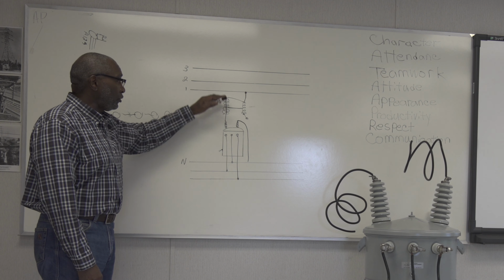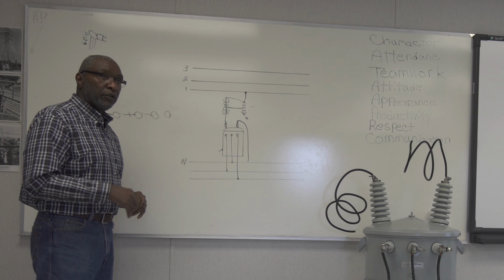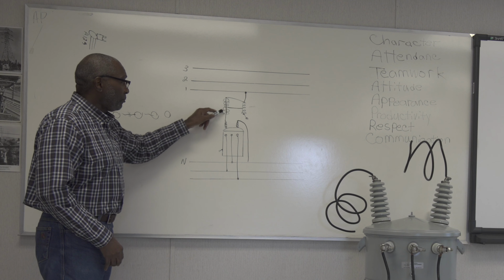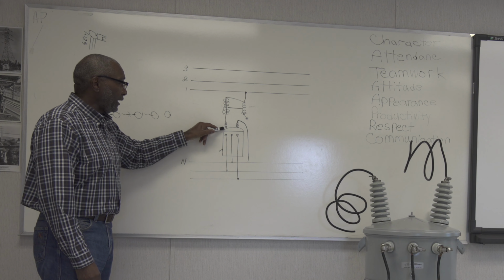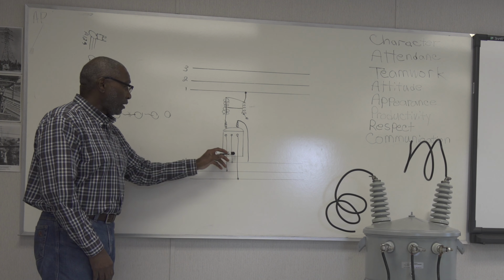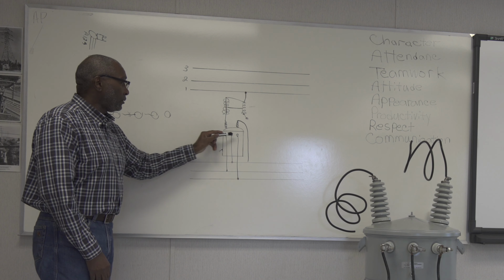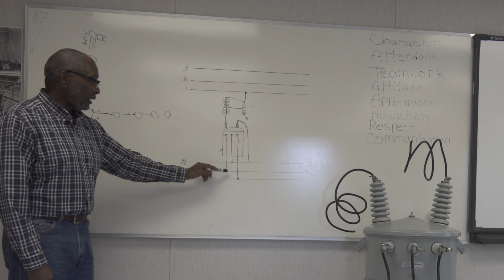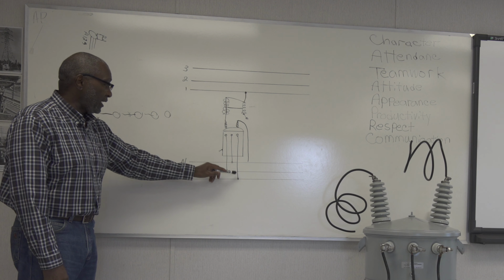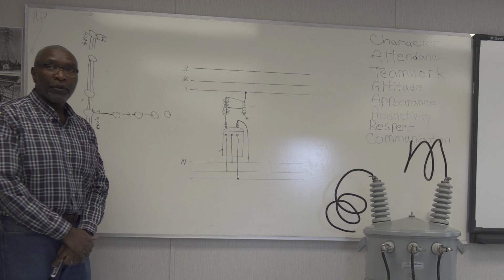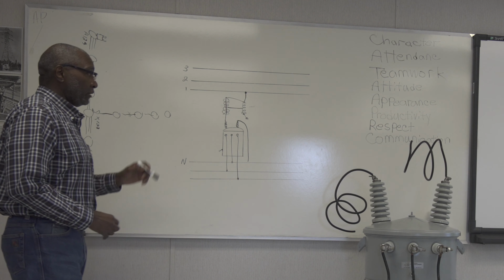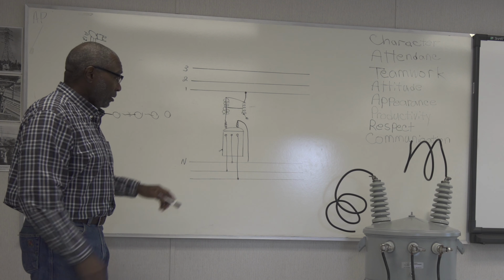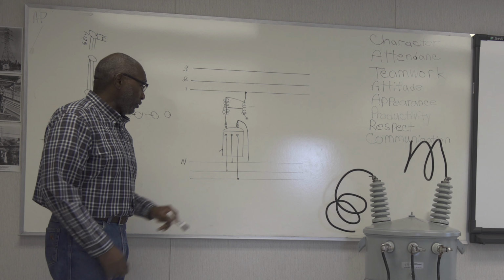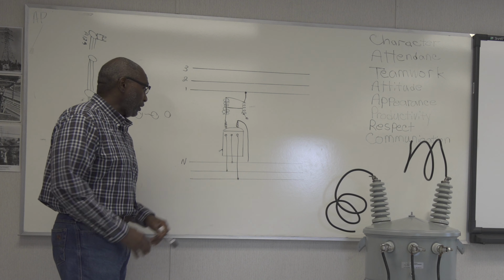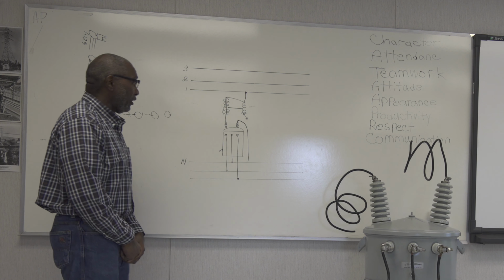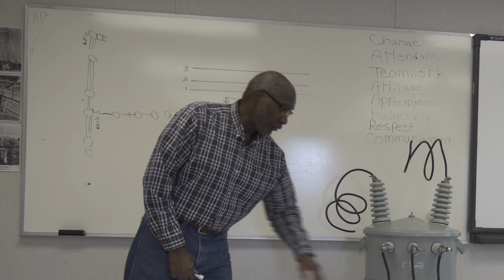So once you energize here with your telescoping stick, that's bringing your voltage into your transformer, coming in on this side, like I said, going through, coming out 120, 120, together 240 volts. And like I said earlier, you can measure on your connectors here, or you can measure on your bushings themselves. Again, some things to remember. On your hookups, you're using your squeeze-ons, your H connectors here for the secondary wire coming together on your low sides here.